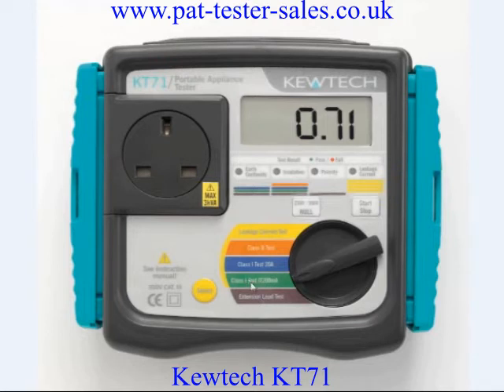The class 1 IT 200 milliamps will do a soft earth test at 200 milliamps plus a 500 volt insulation test.